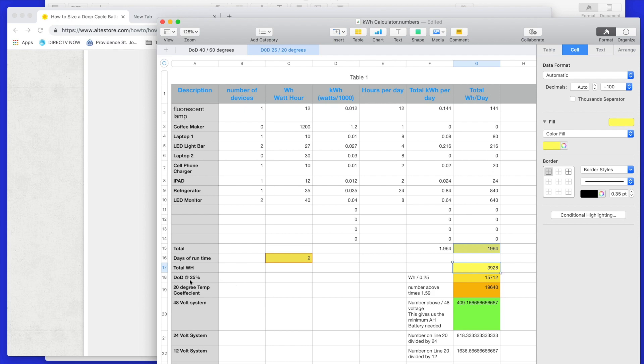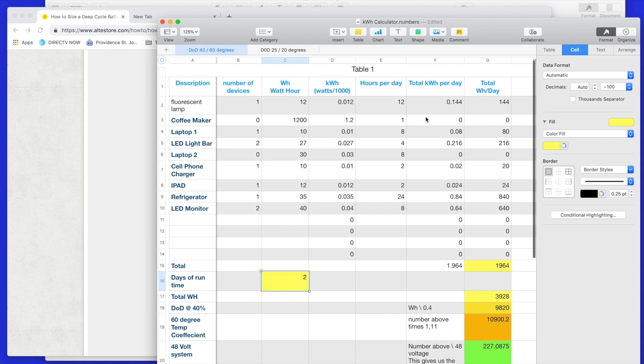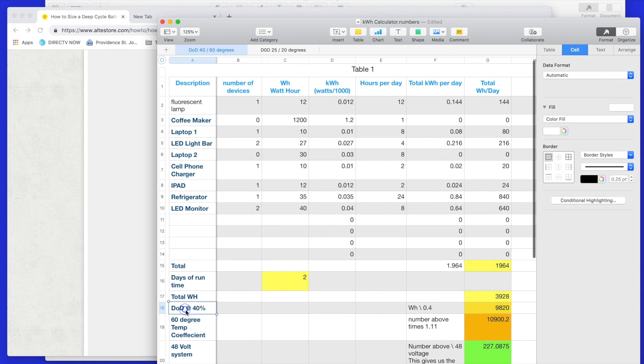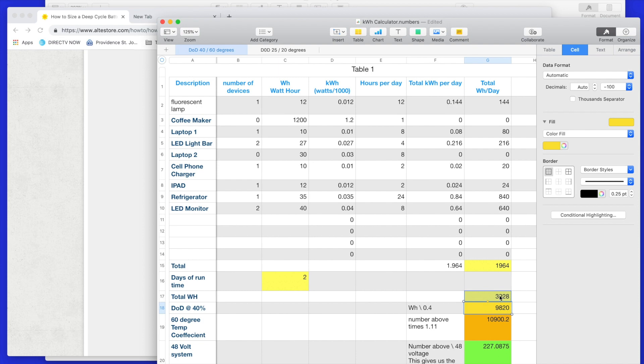So in this scenario, I'm in a different spreadsheet. I should go over here to the one that's average. In this scenario here, same thing, I've just changed the depth of discharge. 40% is pretty average, i.e. we're going to go from 100%, we're going to draw it down to 90, 80, 70, and 60. That difference from 60 to 100, we've drawn down 40% of that battery. Again, we don't want to go to the 50% mark. So this is an average, 40%. We take that watt-hour total, and we divide that by 0.4. That gives us this number here.